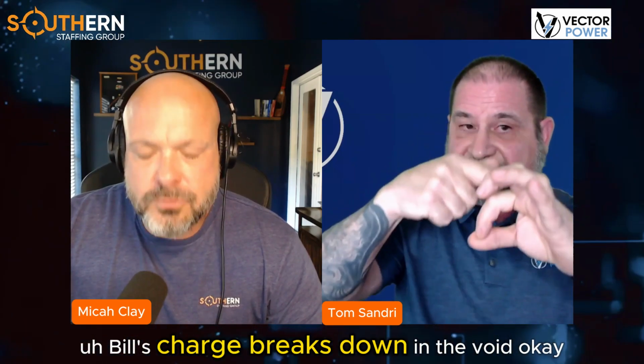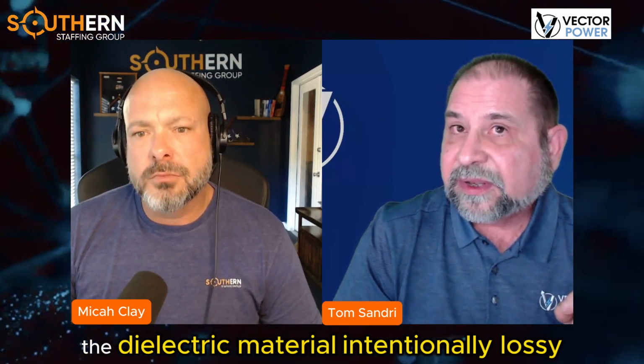Let's go back to the whole concept of partial discharge. Remember the void discharge builds charge and breaks down in the void. So what if I design the insulator, the dielectric material, intentionally lossy? Basically, I'm going to give you a paper cup and you fill it with water until it overflows. Discharge. Now I give you the same cup, but I perforate it.